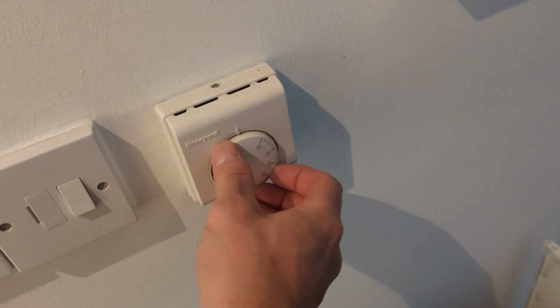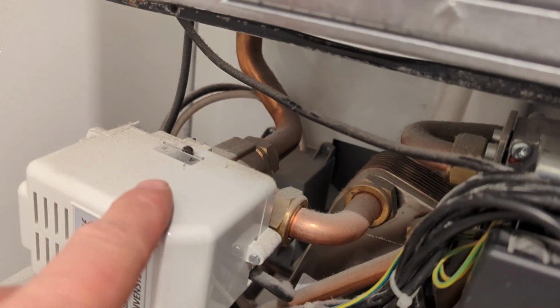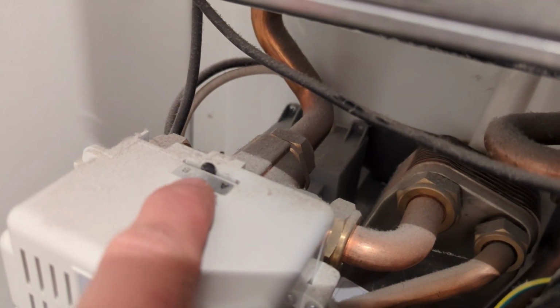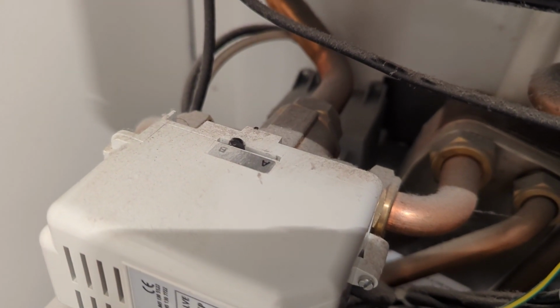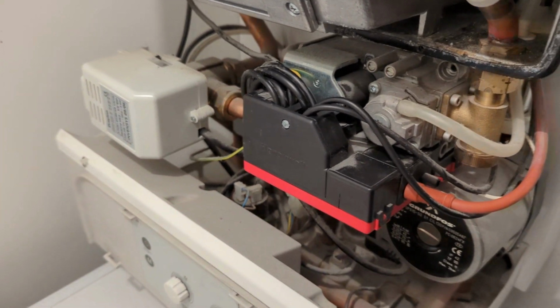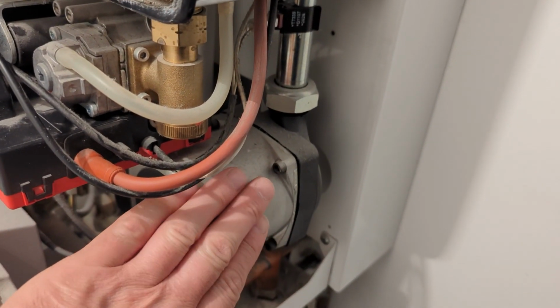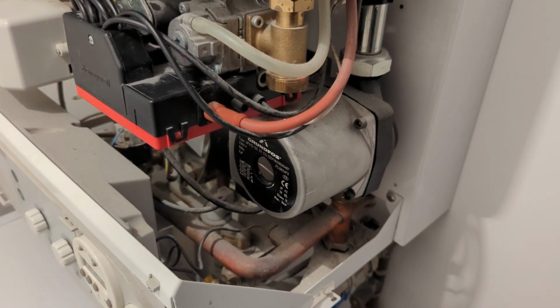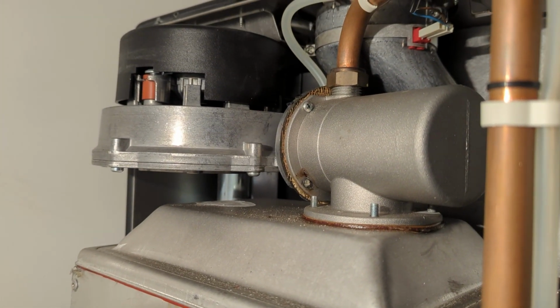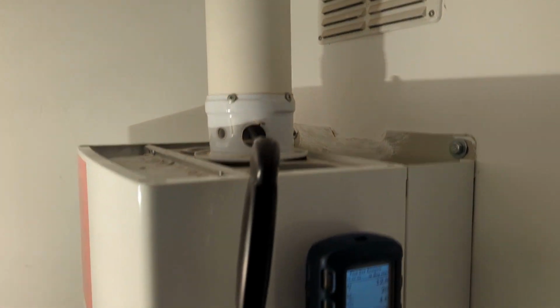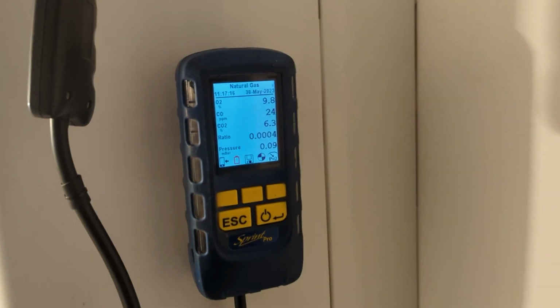so that's one thing ticked off. Now let's try the heating. Turn the thermostat up. We can see the diverter valve going over to heating mode, which is the B. That's a good sign. The pump kicks in, another good sign. So it's going through its ignition sequence, the fan kicks in, and the boiler ignites. And we have heating. So all that over a little flue thermistor. Now that's changed, everything's working, we've got heating and hot water again.